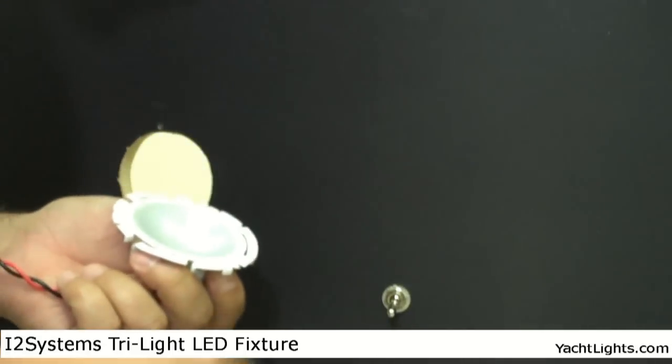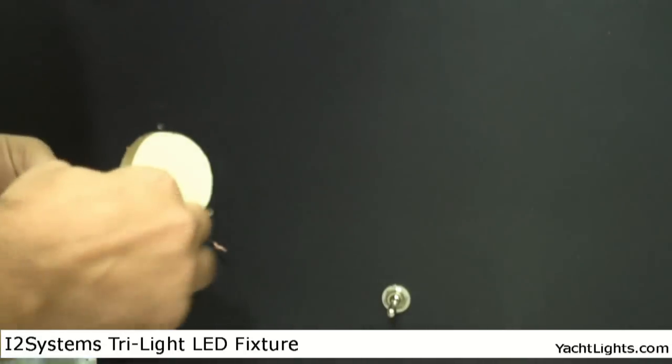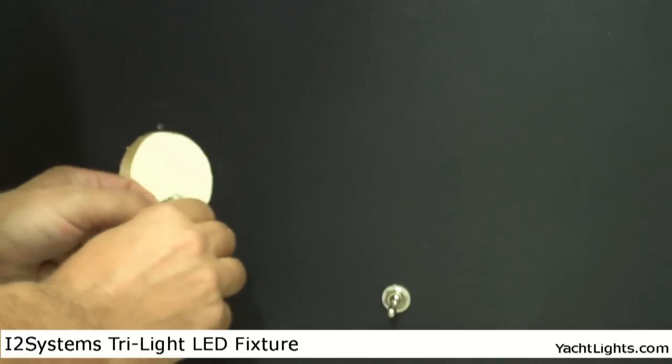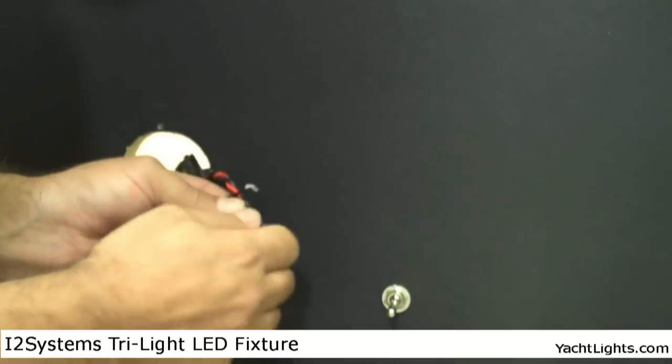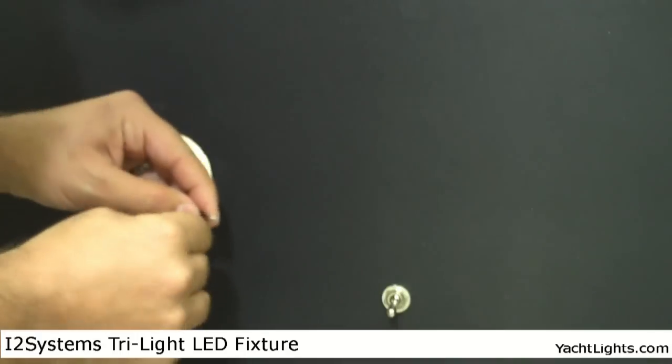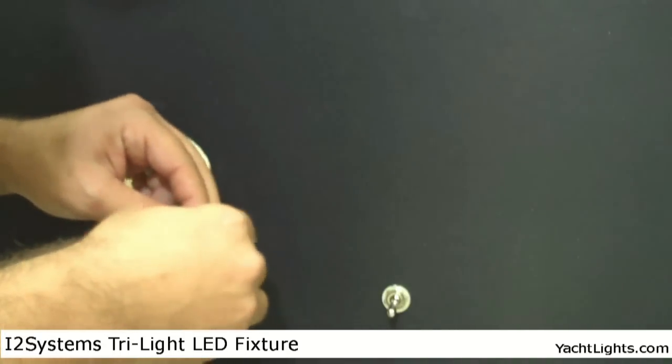First thing you have to do is put it in place and you're going to make your wire connections. So you're going to connect the red to positive, black goes to ground, and this fixture will work with either 12 volt or 24 volt.